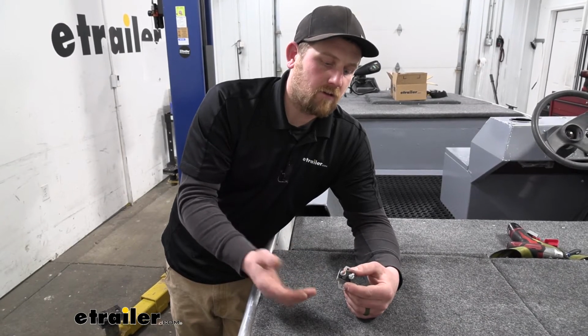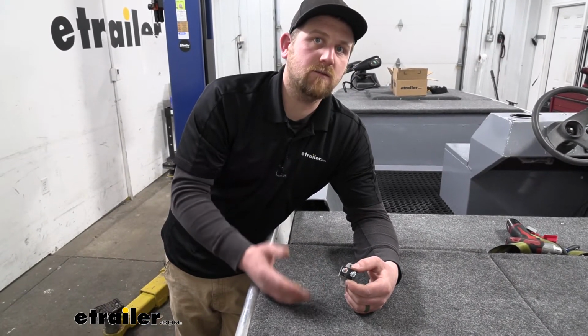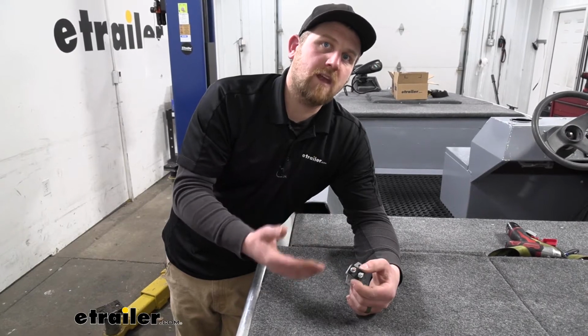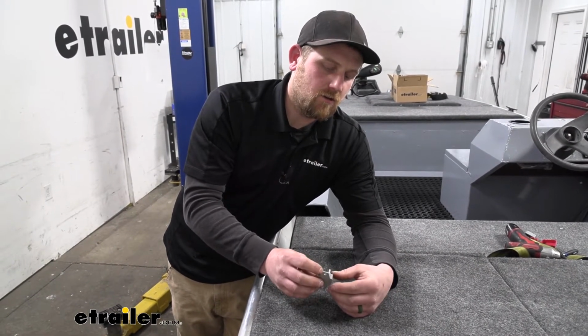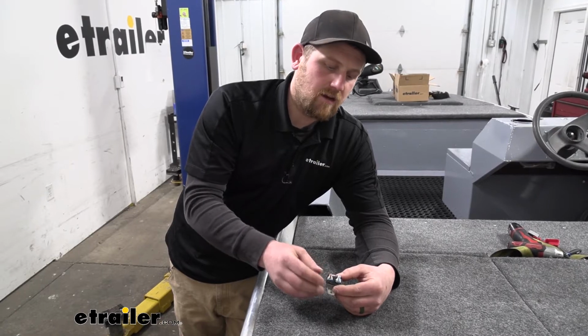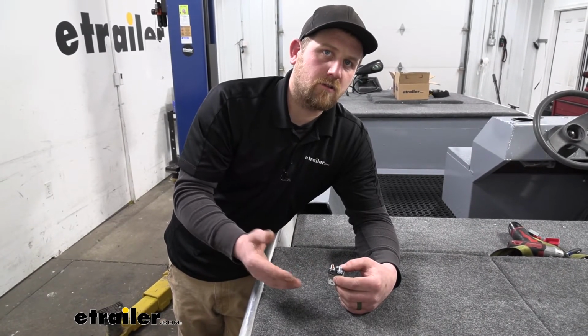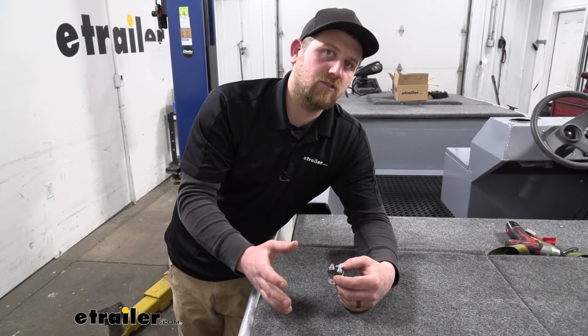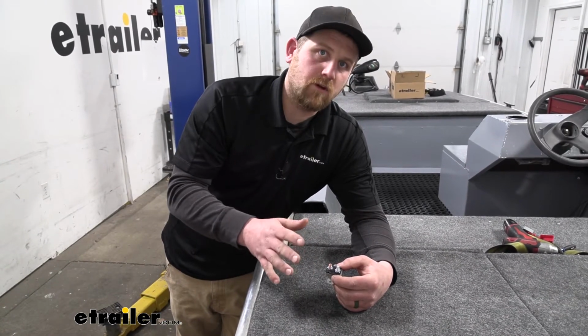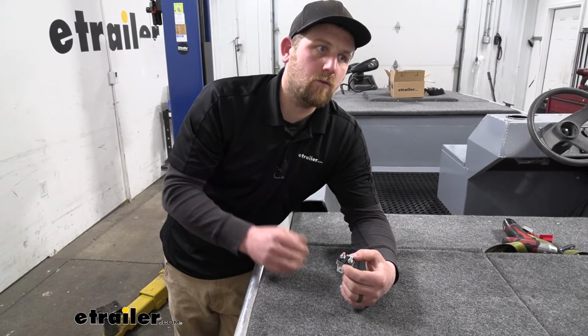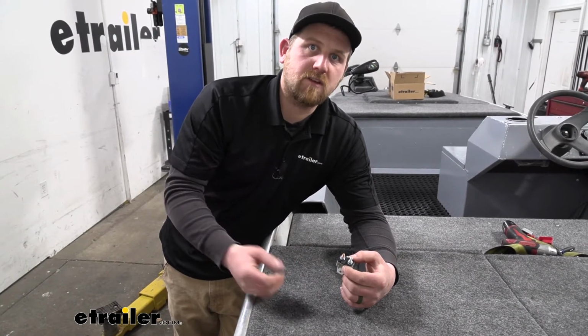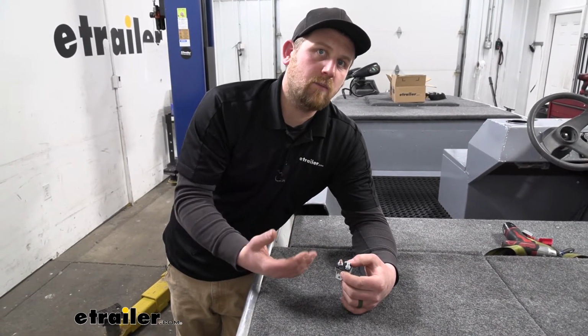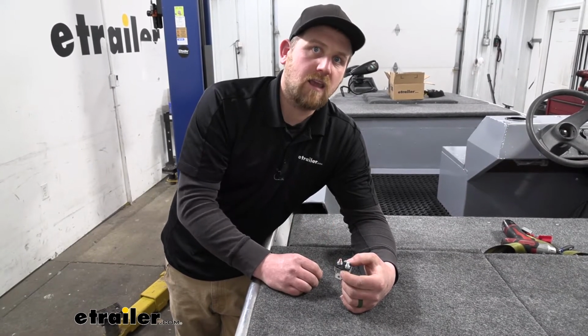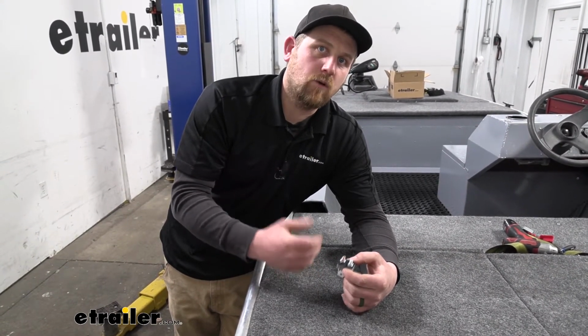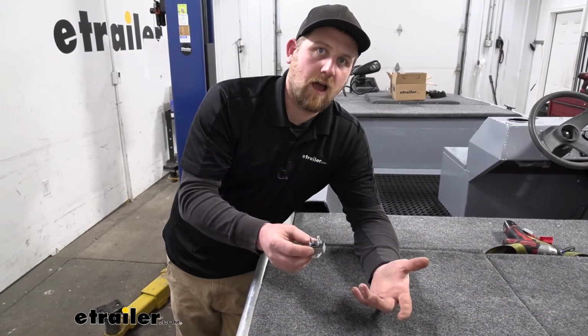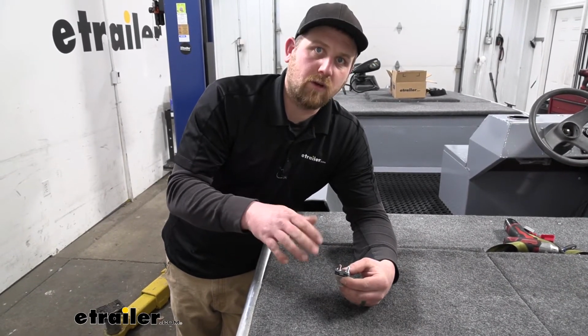Another way, if all else fails, is to use an amp meter to measure that amperage. Typically you'd get a breaker just a little bit larger than what the product actually draws. That gives it some wiggle room, because often when you turn on that accessory, right when it fires on there can be a spike in the amperage it's drawing, and you want to avoid tripping your breaker for no reason. It's really common, so you just give it a little wiggle room.